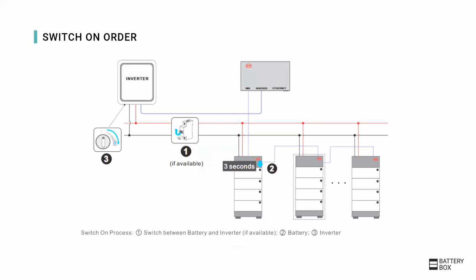After the cabling is done, the general startup procedure for the system should be first the system switch between the battery and the inverter, if there is any, then the battery or batteries, and then the inverter. The batteries are switched on by pressing the LED button on one LVS module for about 3 seconds.